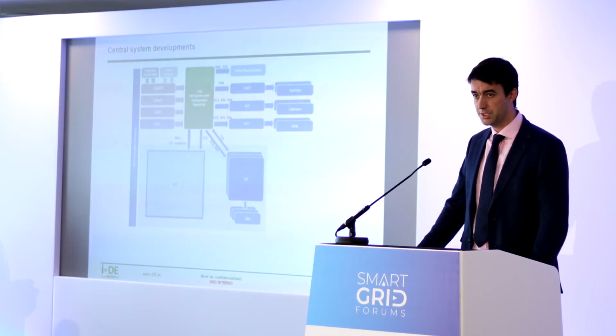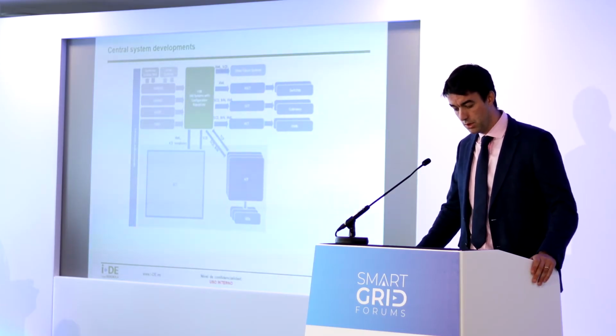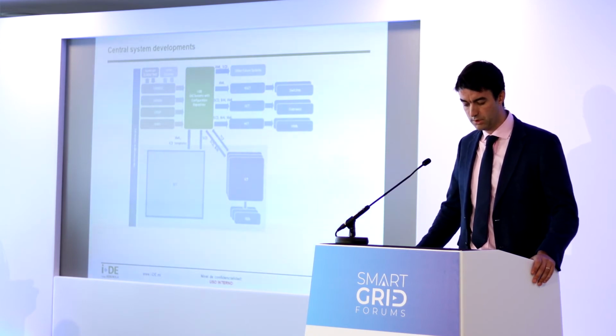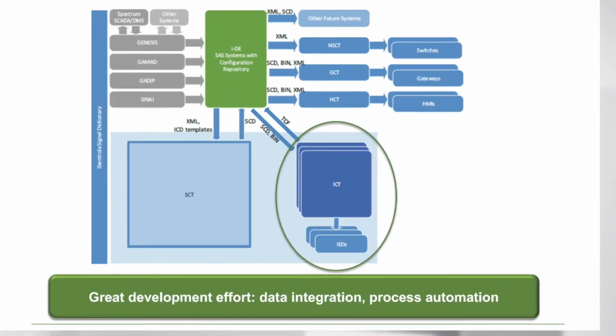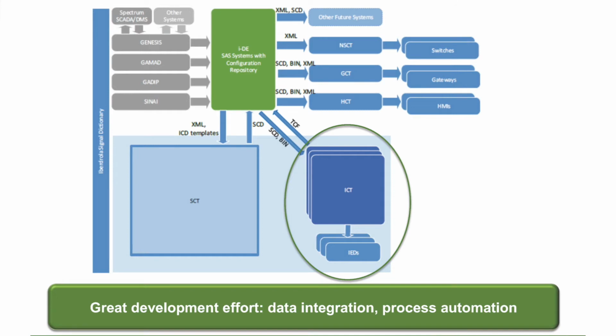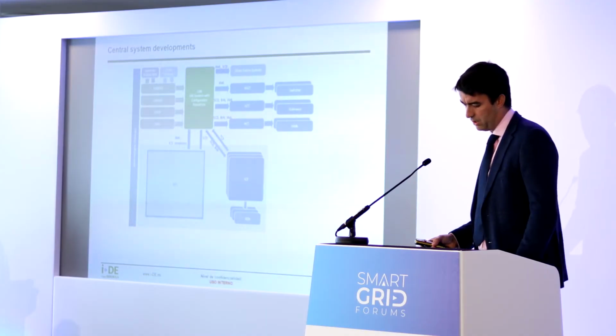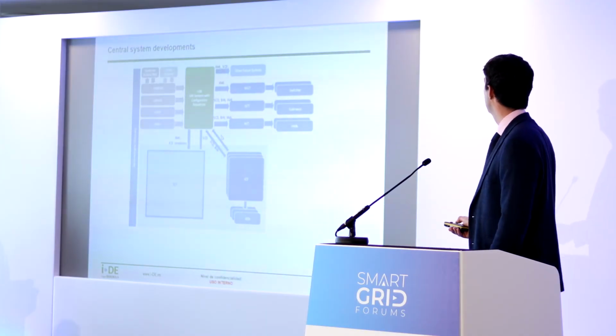But this is to digress, and to go back to our central systems, which have all the information for configuring the substation, and will send all this information to the substation configuration tool. This means that the SSD file, the SCL file, is insufficient. It's not enough to send to the substation configuration tool. Therefore, Iberdrola have had to diverge somewhat from the existing standard. And we have had to define our own XML file, which we call the CNF file.